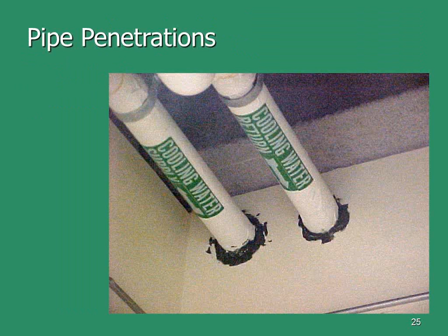I see this a lot of times: piping that has an insulation jacket. We want to interrupt that insulation jacket, caulk the penetration, reduce it and caulk it, and then start the insulation on the other side. Because insulation is absorptive, but it is not a barrier.